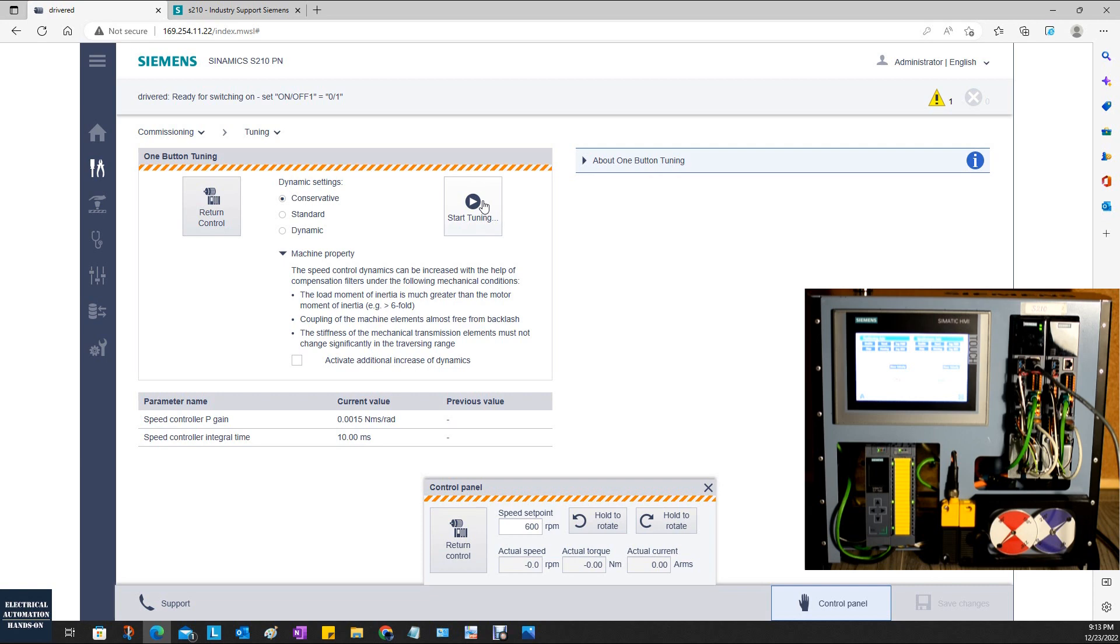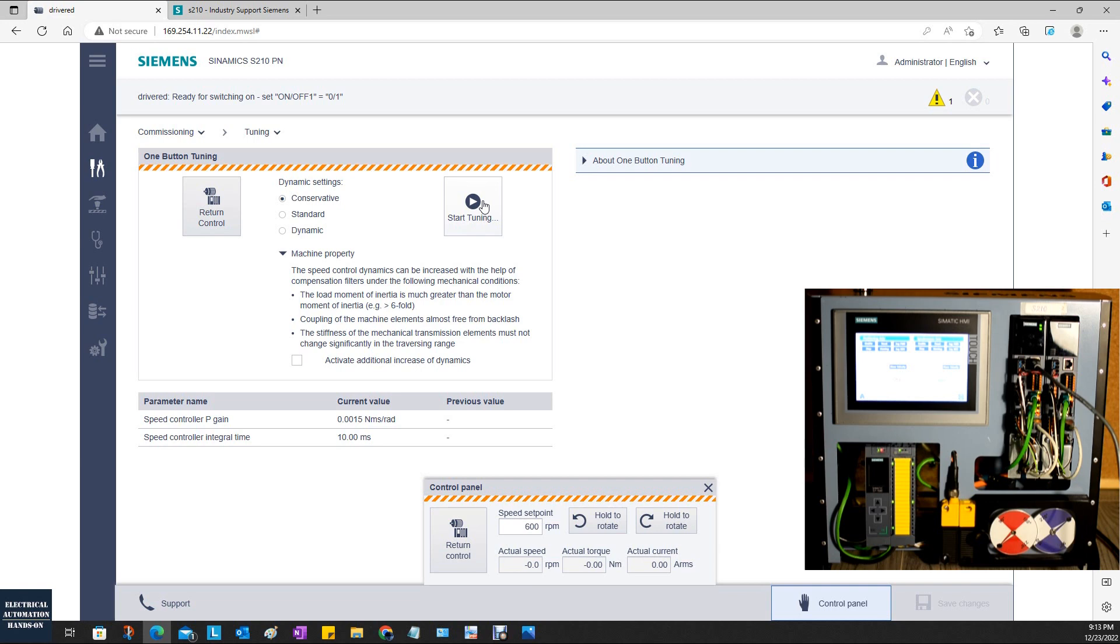Once we start this auto sequence, it will run the servo drive on its own. It will run the servo drive very fast in a short moment. You need to be very careful about your mechanical system. Also, you better prepare safety and monitor if the drive has something wrong. To better tune the motor, we definitely like to connect the mechanical load to the servo drive, to the motor, so we can tune better parameters.